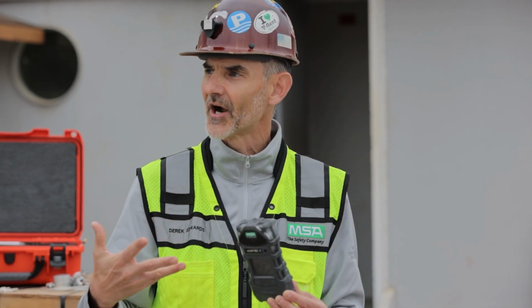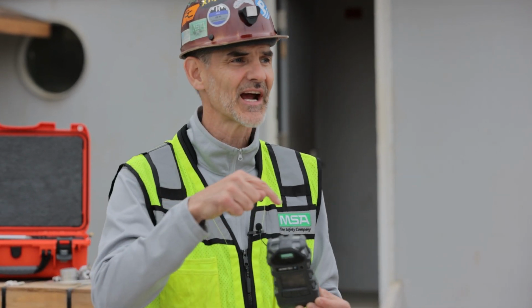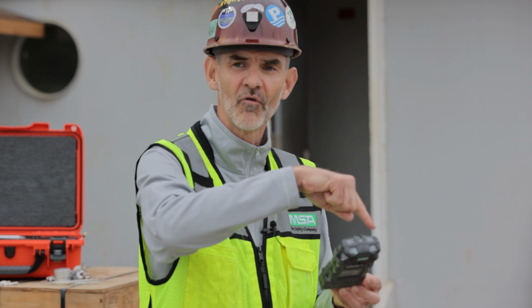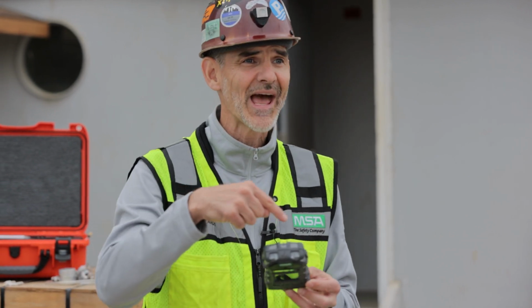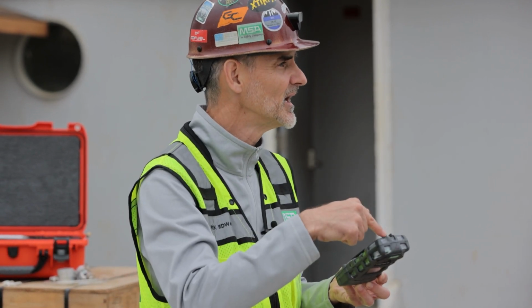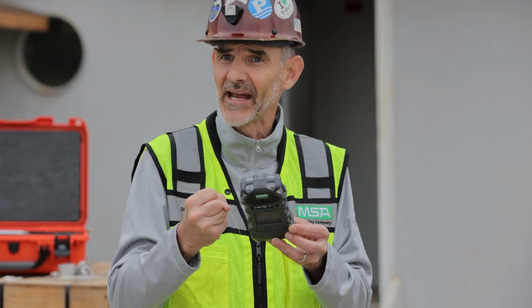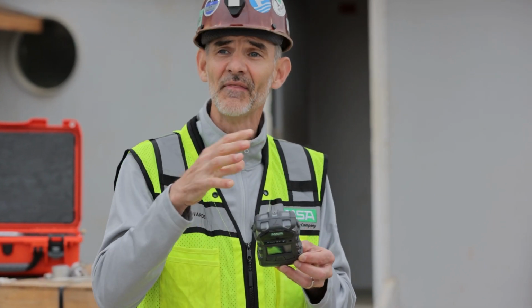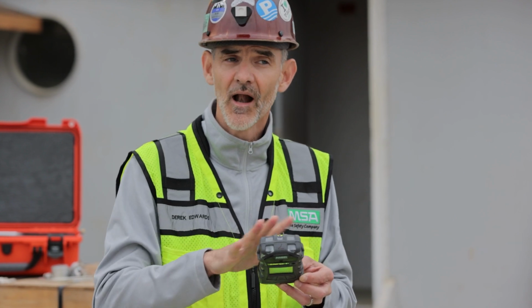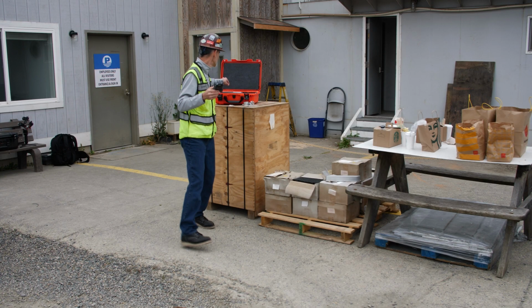So what I did there was I checked the integrity of that pump system. If we had a leak in that system, it would not have passed that test, because it sucks up tight, passes the test, and then moves on. Okay?